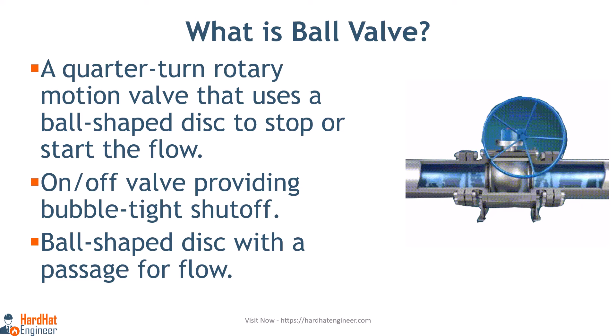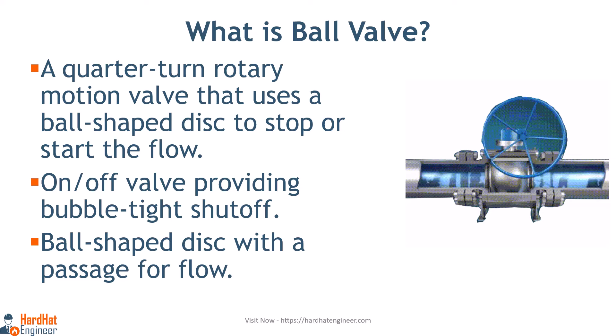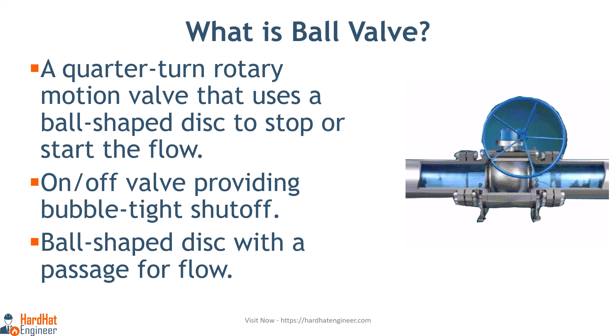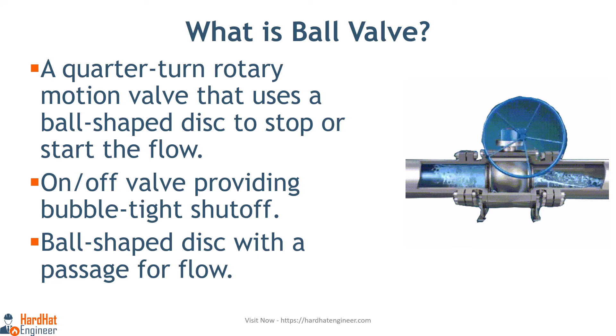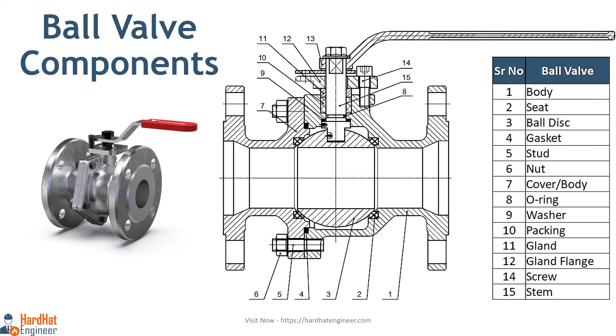What is a ball valve? A ball valve is a quarter-turn rotary motion valve that uses a ball-shaped disc to stop or start the flow. It resembles a plug valve in many ways. Most ball valves are quick-acting, requiring a 90-degree turn of the valve handle to operate. For large-size valves that require considerable force, a gear-operated actuator is used, and a small hand wheel is enough to operate a fairly large valve.